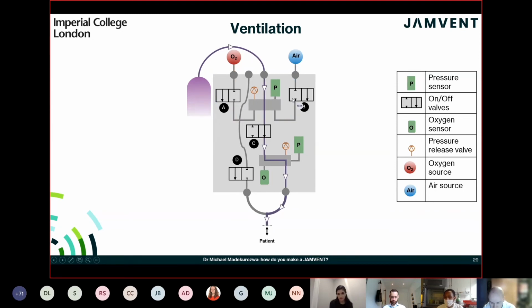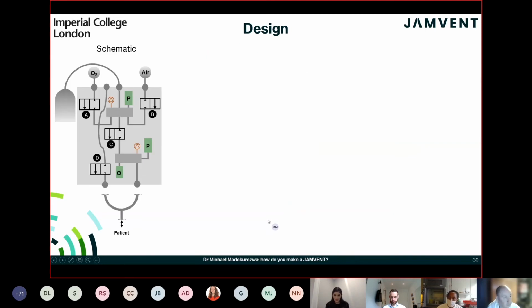So the air and oxygen lines are closed, and the single breath is delivered to the patient by the opening of valve C, straight down here to the patient. And then this cycle repeats, and this is how ventilation occurs. So here's a schematic of what the system looks like, and I've been showing you a schematic all along, but it's not actually what the system looks like.